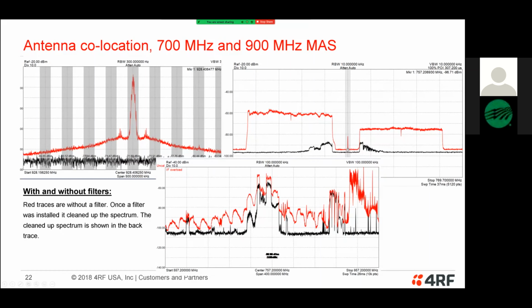There's a window in the upper left-hand corner showing a 928-952 MAS network. The one in the upper right is a 700 megahertz system. The two big carriers on either side are Verizon's LTE network on the left and FirstNet on the right. Those were strong enough that they were interfering with our tiny SCADA signal in the middle. When we installed the filter, it took those interferers down to the black line, and we lost only about 2 or 3 decibels of insertion loss, but performance radically improved because we removed the interference.